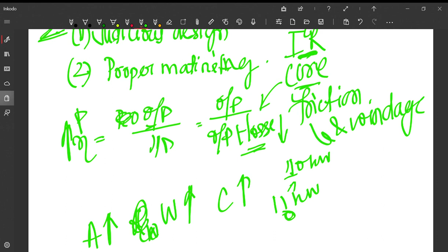The second most important thing was the proper matching. Now, to drive a 10 kilowatt load, for example, we should always try to use a motor having more than 10 kilowatt of driving capacity. In that case only could we get maximum output, because a motor with more than 10 kilowatt capacity will anyways have some losses. Now, if to drive a 10 kilowatt load I use a 10 kilowatt motor, obviously it will not give 10 kilowatt output, because a few of the power from this will be getting wasted because of the losses. So the proper matching of the load as well as the motor or any machine is very important in order to get an energy efficient electrical machine.